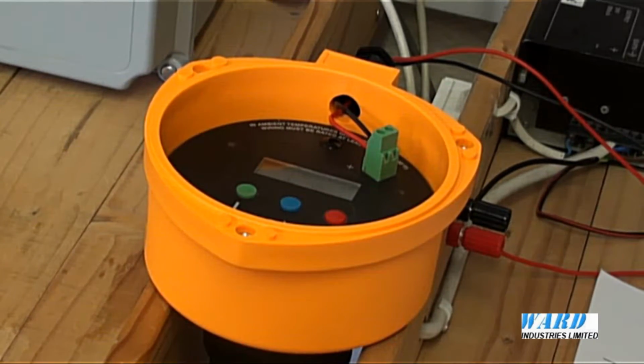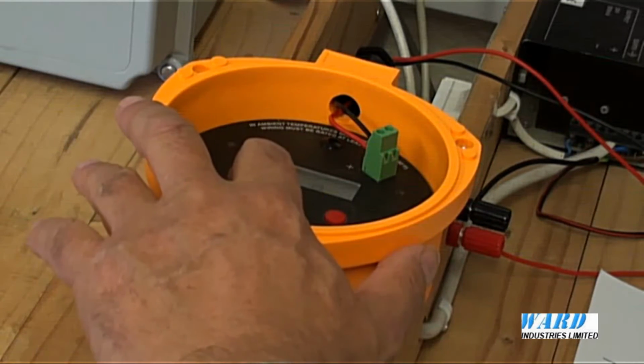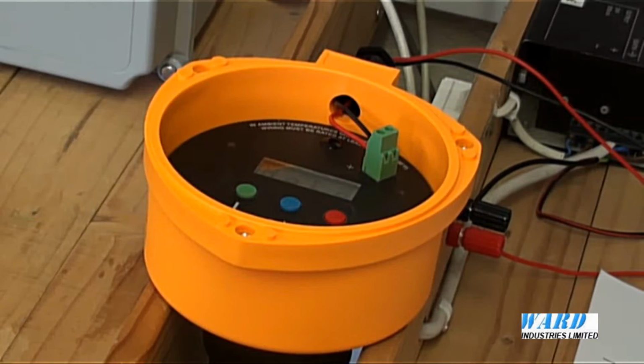Low. With option low, the output will decrease to 3.6 milliamps and remain there until the correct target echo is recovered. Hold. This is the factory default condition. The current will freeze at the value of the last reading and remain there until a correct target echo is recovered.